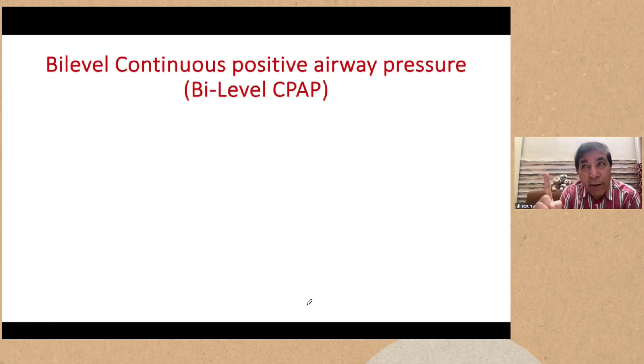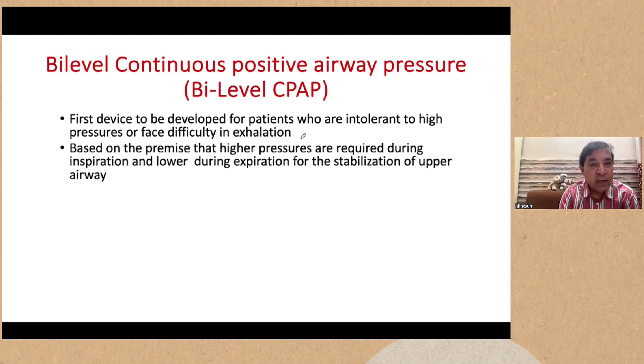We know that to stabilize upper airway, you need more pressure during inspiration and less pressure during expiration. So that led to two pressures, one pressure for inspiration and one pressure for expiration. So you use two CPAPs to stabilize upper airway, and that led to the development of what is called bi-level CPAP. So this device is not used for ventilatory support. It is not going to enhance the ventilation, but it is basically two pressures used to stabilize upper airway during inspiration and expiration, and they are different pressures.